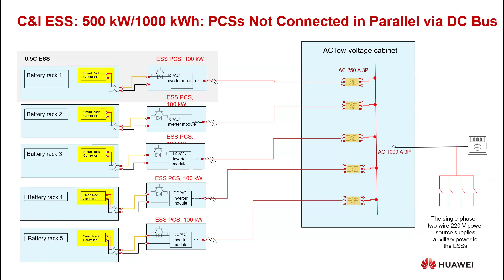But I would like to add some more information about it. It's just a recommendation from the manufacturer. Whatever the circuit breaker, I mean this main circuit breaker, it will be adjusted by the designer, who must include information like the cable length, so what our line impedance would be, what the thickness of the wires would be, and all of those values are supposed to be included in designing or picking the right circuit breaker. It's quite usual that we just check the manual and use the circuit breaker suggested by the manufacturer. However, please remember you must always include your electrical diagram and all the components which are in your grid and how they can affect each other.